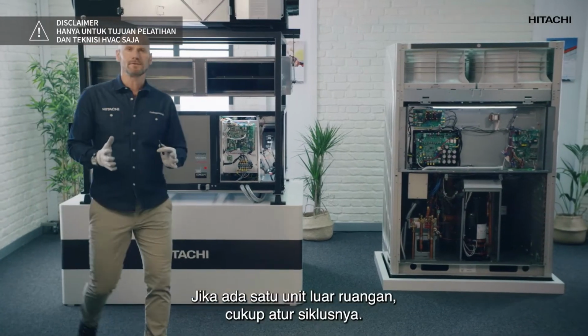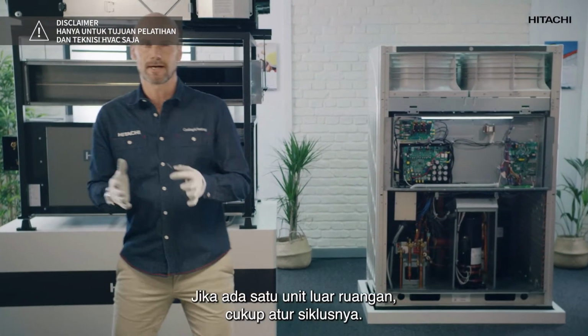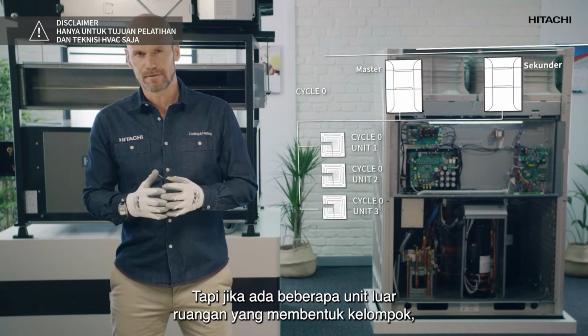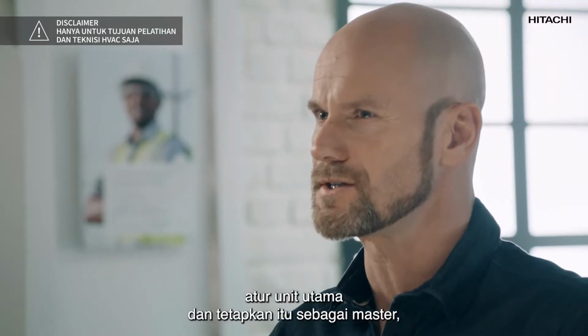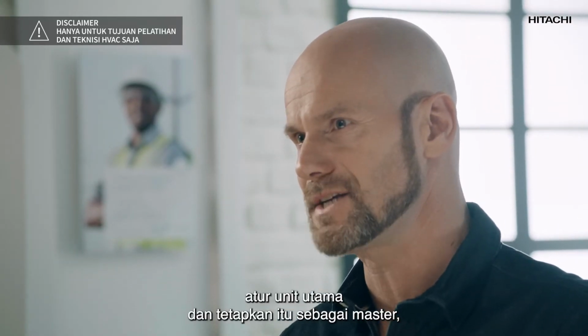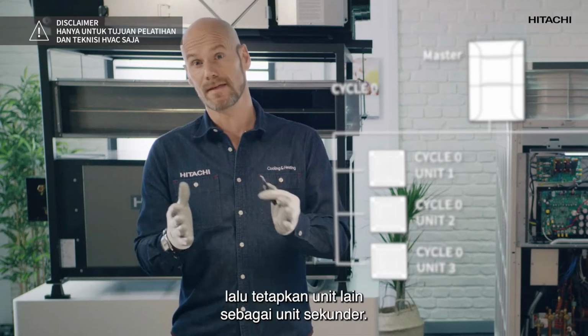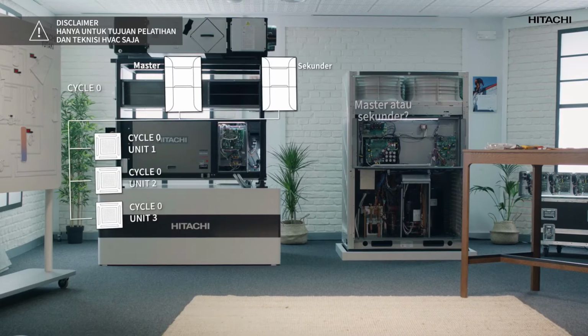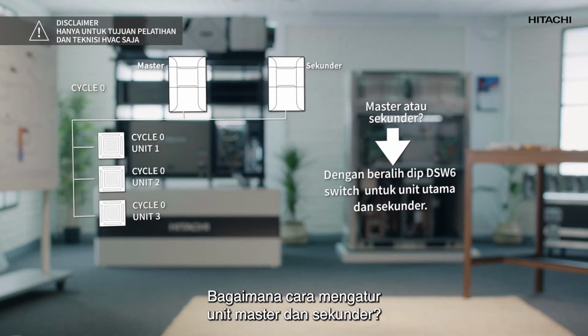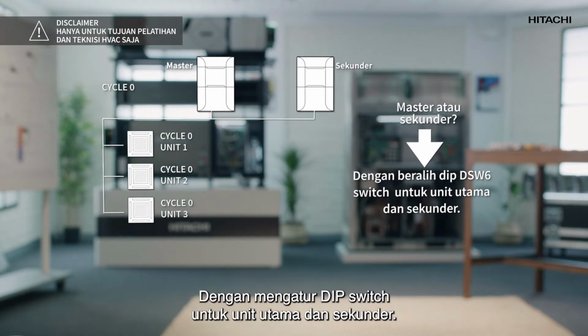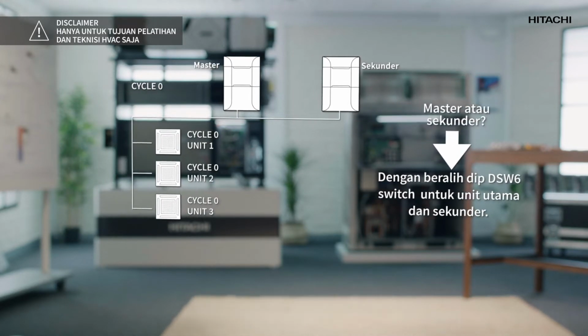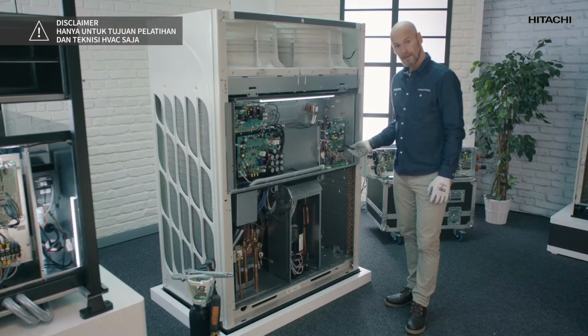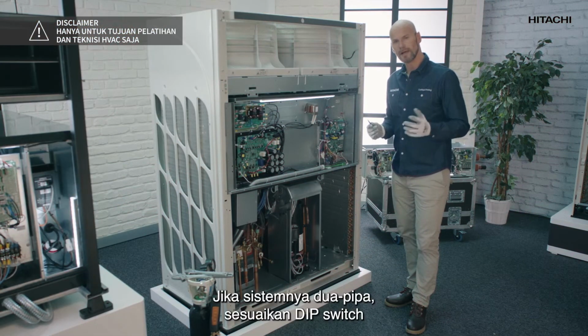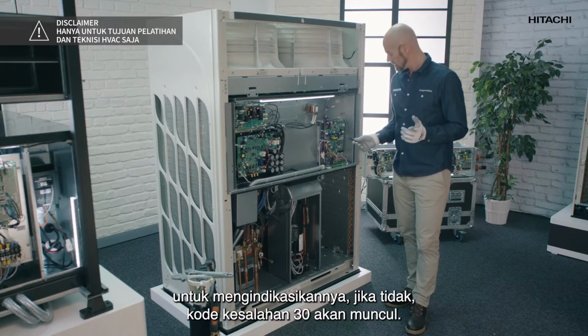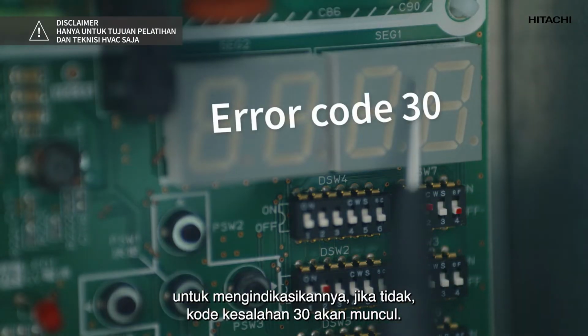If we have one outdoor unit, we only have to adjust the cycle. But if we have several outdoor units that form a group, we have to adjust the main unit, telling it that it is the master, and tell the rest of the units that they are secondary units. How do we tell them who is master and who is secondary? By setting the dip switch for main and secondary units. If it is a 2-pipe system, you will have to adjust the dip switch to indicate it, because if you don't, the 30 error code might be displayed.